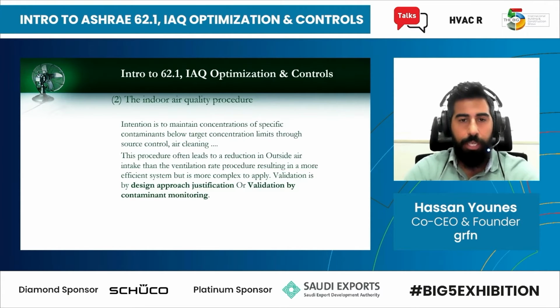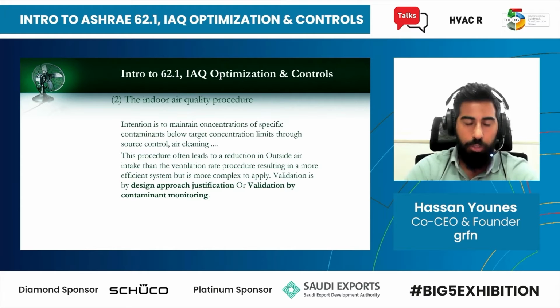Now, the indoor air quality procedure is basically looking at contaminants. So you need to figure out what kind of contaminants and pollutants will be emitted in that particular room. And then based on the outdoor concentration of these contaminants, you can do a mass balance equation to come up with the required outside air to be delivered. Now, it's not widely used because it needs more work to be done, and it needs more knowledge about what the potential contaminants in the building are. But it normally does end up with lower outdoor air rates compared to the ventilation rate procedure. So there might be some savings here, but it's more complex and not widely used. And some jurisdictions do not accept it as a way to comply with the standard.